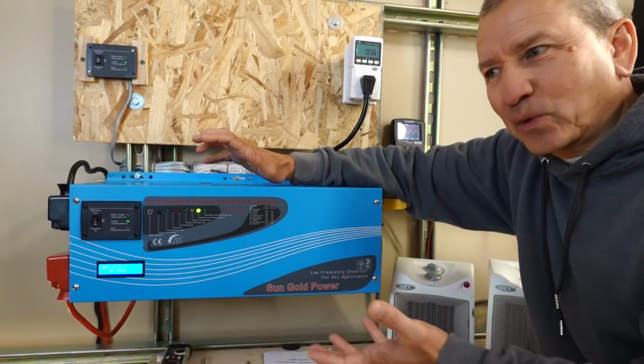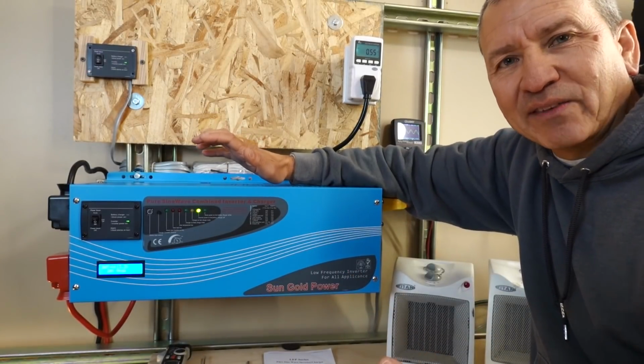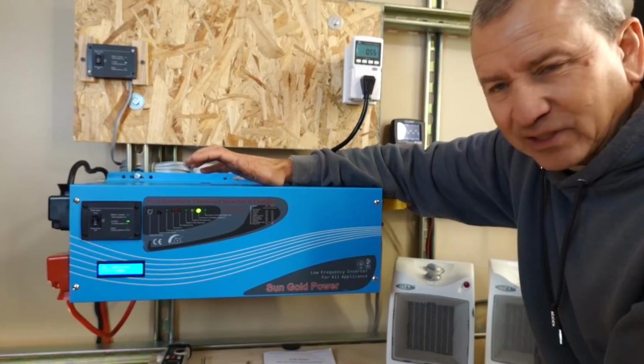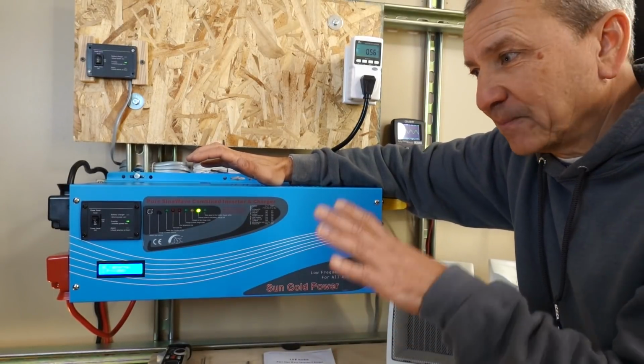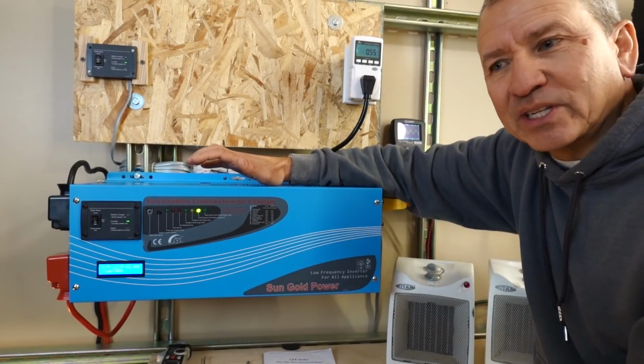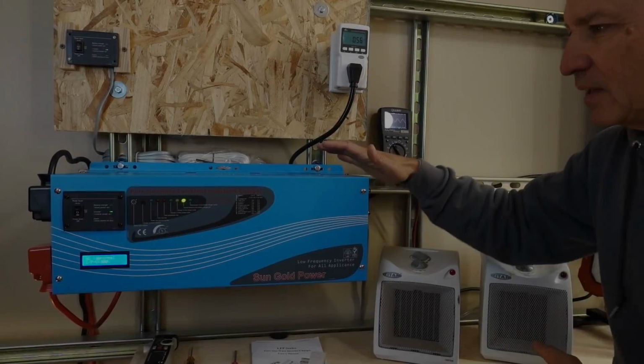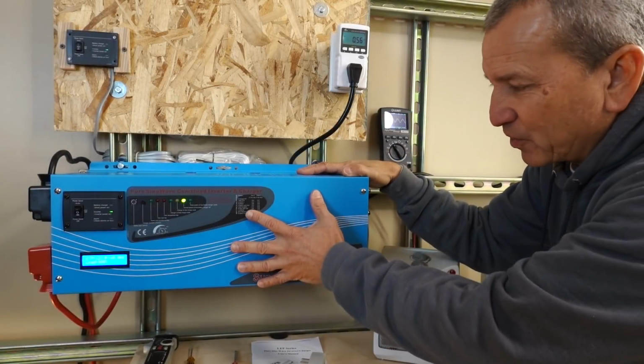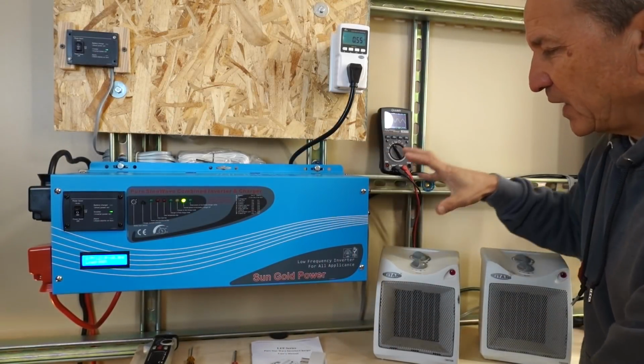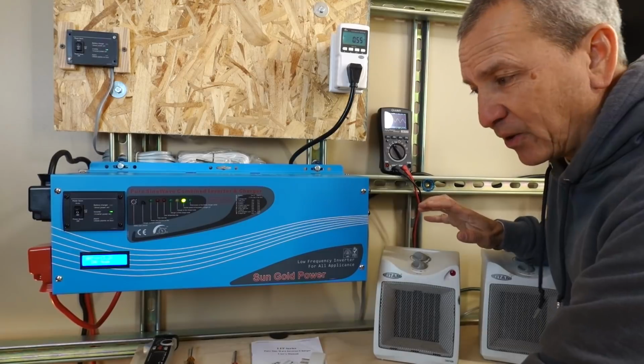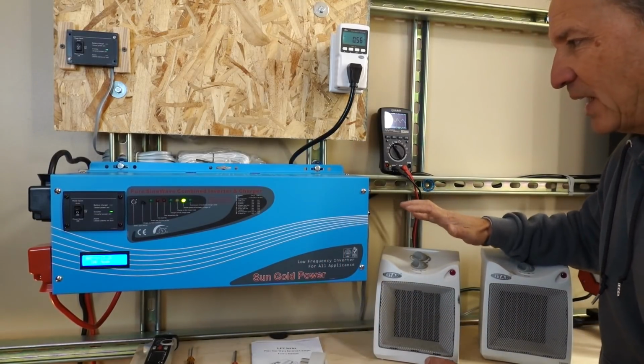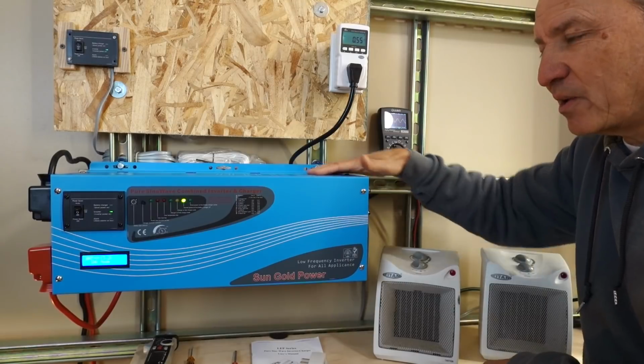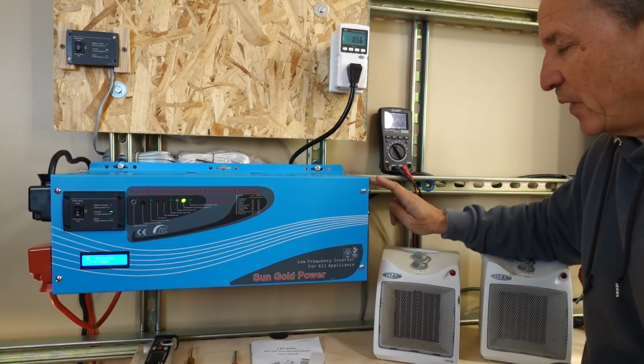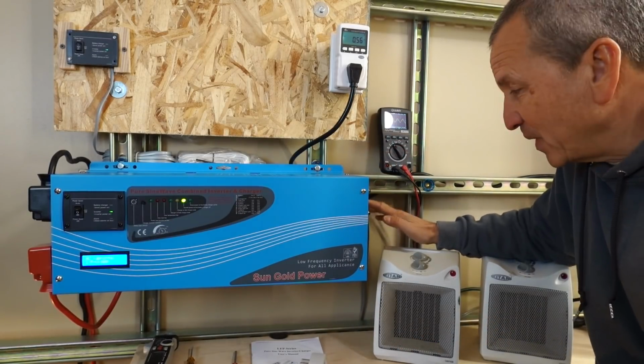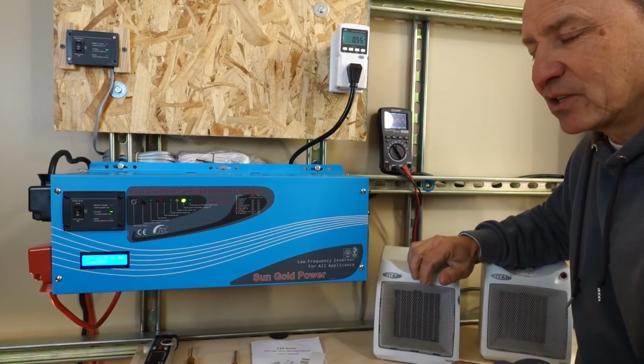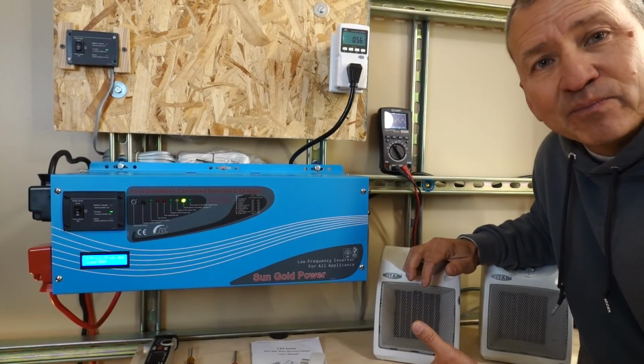But like I said, the unfortunate part is that you can't control that level with this inverter. You basically have to wait for your batteries to really hit that low battery disconnect point first. So now we've got the inverter running in inverter mode. It's basically generating AC power from the DC power coming from the batteries, and we're running in grid priority mode. That means when there's AC power detected coming in, it'll automatically switch to that AC pass-through mode.